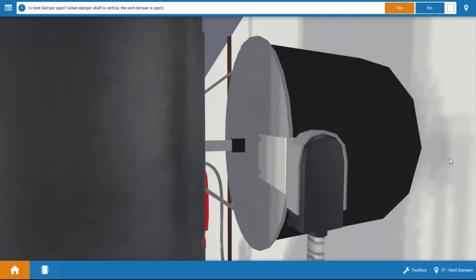This is similar to ensuring that you close the damper on a fireplace when it's not in use. Now, if the vent damper motor has actually driven the damper open, the shaft right here would be vertical, and we can see that in fact it is. If the vent damper motor is not energized, the shaft would be flat or horizontal. So the vent damper is in fact open.